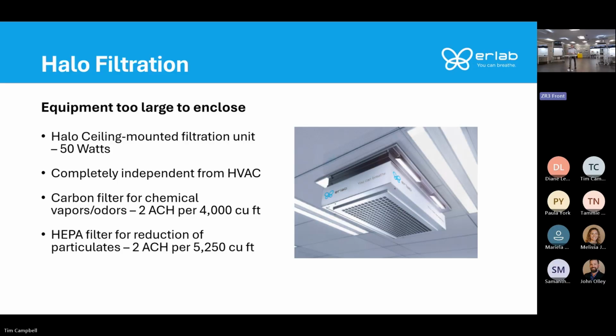The halo is going to increase the ventilation and the effectiveness of the space. It's going to improve basically your HVAC system because it's going to improve the mixing of air. The carbon filtered version is going to add 2 air changes for every 4,000 cubic feet of space. So think a 400 square foot lab with 10-foot ceilings, you need 1 unit. 800 square foot lab, you need 2 units. The HEPA filtered version, there's less resistance to a HEPA filter, so we're pulling a little more CFM. So you're going to want one for about every 525 square foot lab with 10-foot ceilings.